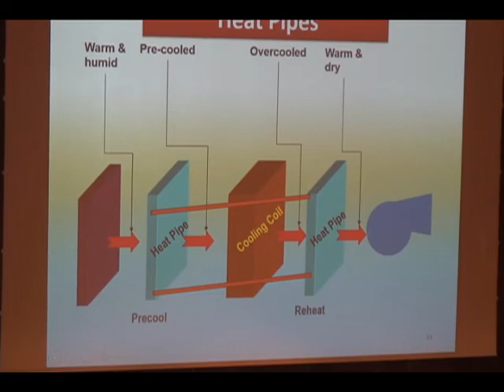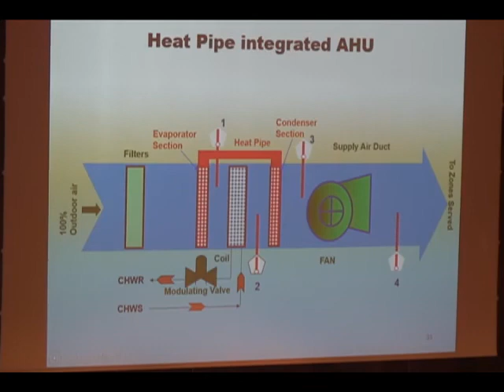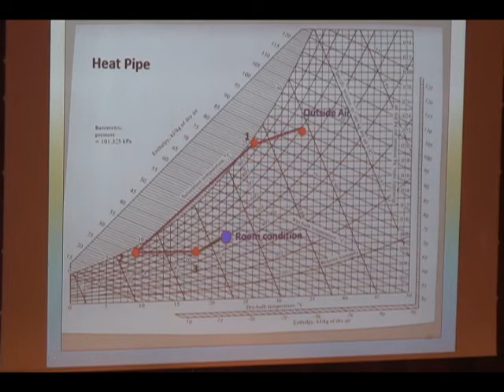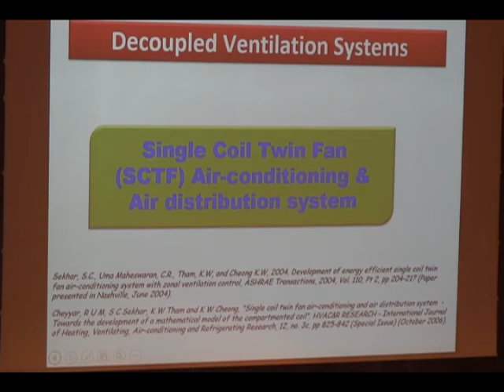It's a passive technology, been found to work reasonably well in hot, humid climates. So it helps us in providing that additional reheat that we would otherwise cannot do. And here it is, the wraparound coil. We'll move on to that. This is, again, a psychrometric way of looking at it. The heat from the outside air is used to reheat the cooled and dehumidified air. We have also developed some other technology which we believe is probably going to be helpful for future designs and developments. When we separate the outside air from the recirculated or cooling air, there's a lot of potential to help us achieve improved performance.